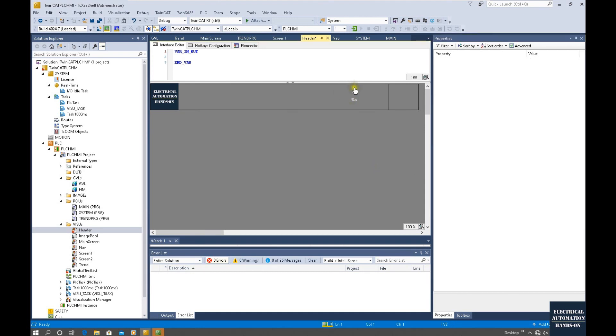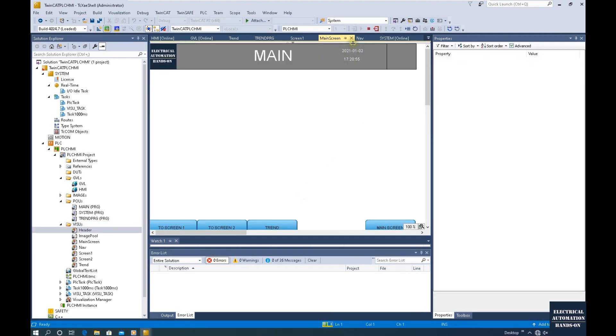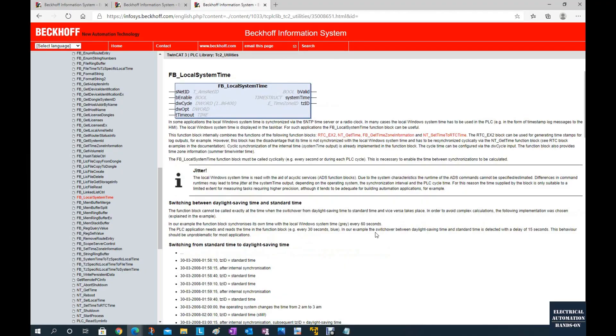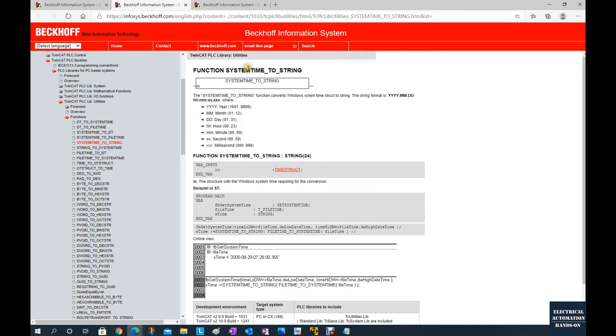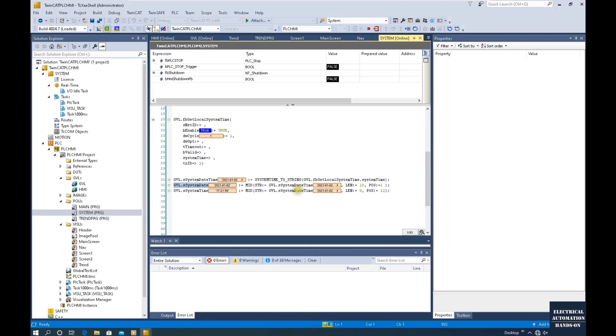There will be two lines. Let's save, build, and login. We can now see the two strings displayed: the first line shows the year, month, and date, and the second line shows the hour and minute. To summarize: we used the function block FB_LocalSystemTime to read the system time, then the function SystemTime_To_String to convert it to a string, then MID to separate date and time, and finally displayed them on the HMI using the %s string format.